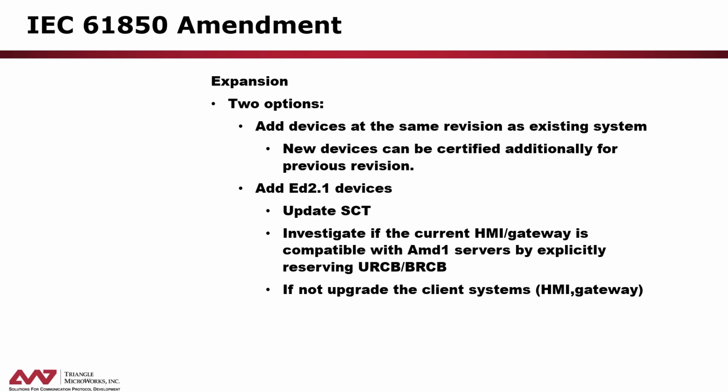And we've gone through and we've investigated all the possibilities with Amendment 1. And really the one issue that's come into play is we made a breaking change in reservation of control blocks. Reservation's been in the standard since late in edition 1. It's been there a long time, but it was optional on the server. We've gone and made it mandatory with this amendment. It should have always been. Lots of history, but it's obvious that had to be. We went ahead and did it, acknowledging there's a backwards compatibility issue.